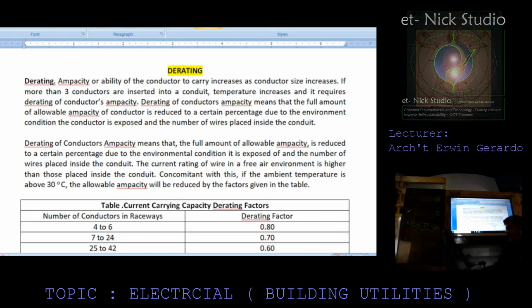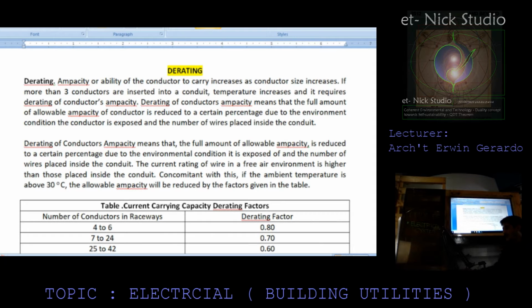Derating, ampacity or ability of the conductor to carry increases as conductor size increases. If more than 3 conductors are inserted into a conduit, temperature increases and it requires the derating of the conductor's ampacity. The derating of conductor's ampacity means that the full amount of allowable ampacity of the conductor is reduced to a certain percentage due to the environmental condition the conductor is exposed to, and the number of wires placed inside the conduit.